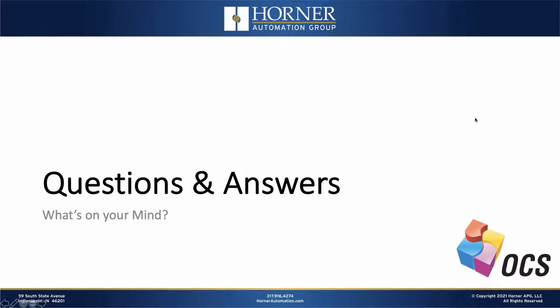This is a question from David Gartner asking about the limitation in Cscape. I mentioned earlier that when you have an interruption in communications between a client and the broker/server, if it's quality of service 1 or quality of service 2 type messaging, there will be buffering that occurs during the communications interruption. And on the client side for an OCS, we're currently limited to 20 messages total that we can buffer. So his question was, after 20 buffered messages, is the 21st message lost, or is it the most recent 20 messages? That's a great question.